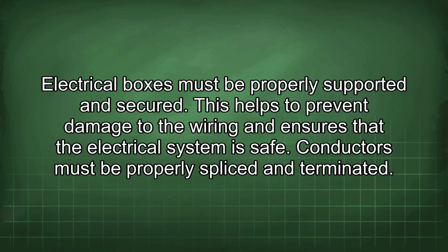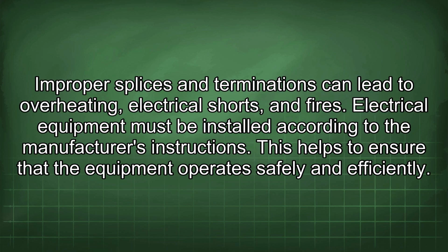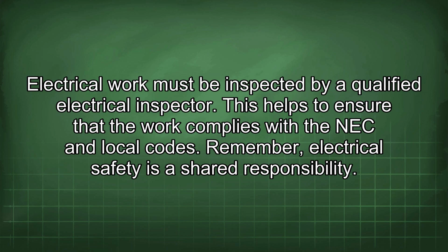Electrical boxes must be properly supported and secured. This helps to prevent damage to the wiring and ensures that the electrical system is safe. Conductors must be properly spliced and terminated. Improper splices and terminations can lead to overheating, electrical shorts, and fires. Electrical equipment must be installed according to the manufacturer's instructions. This helps to ensure that the equipment operates safely and efficiently. Electrical work must be inspected by a qualified electrical inspector. This helps to ensure that the work complies with the NEC and local code.